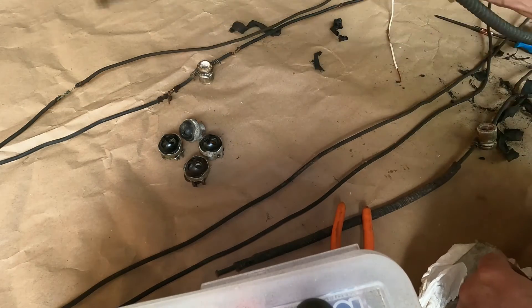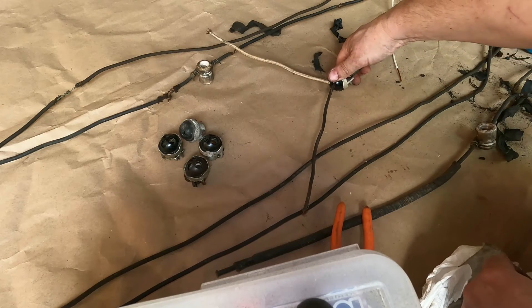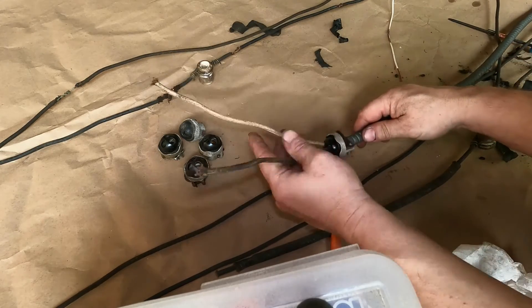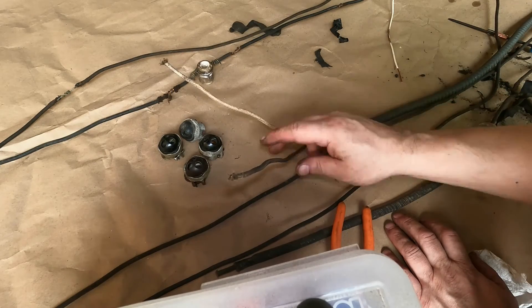I have never seen them used as a splice in between knob and tube wire. If you did see that, that would be an inappropriate connection and you want to run a new circuit to the BX wire.